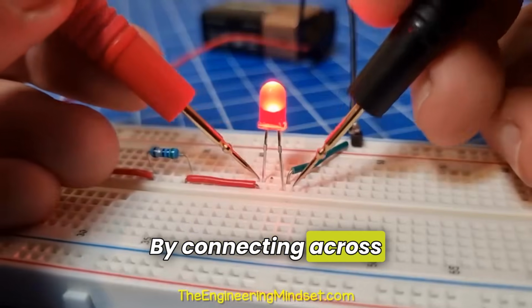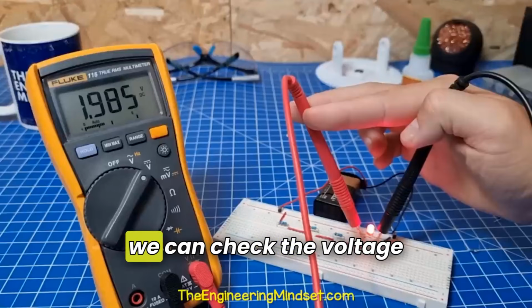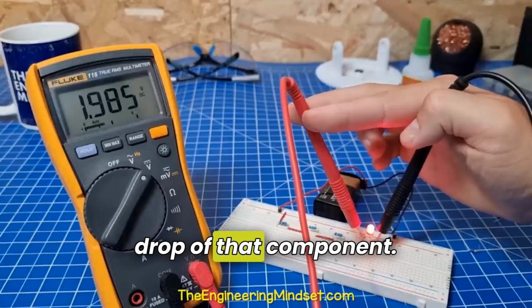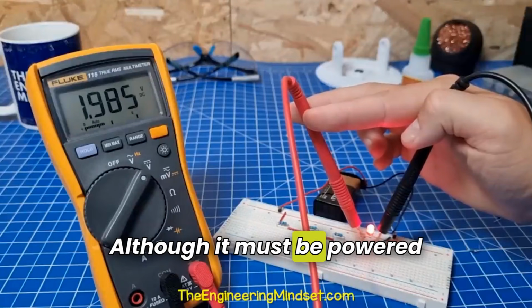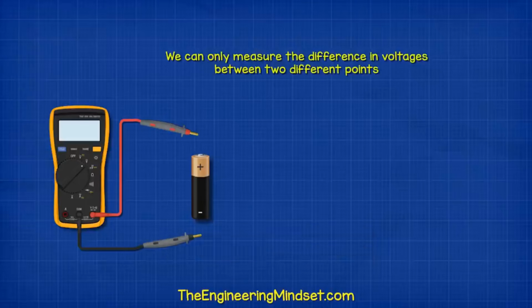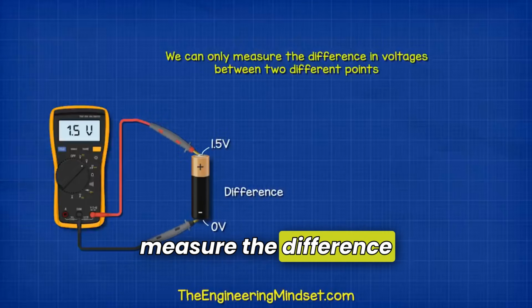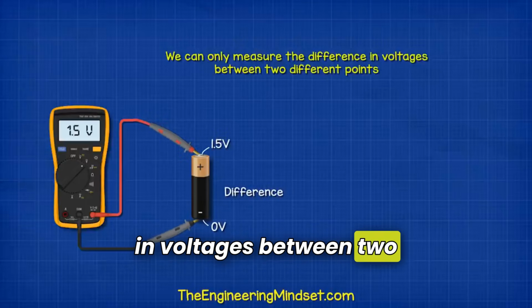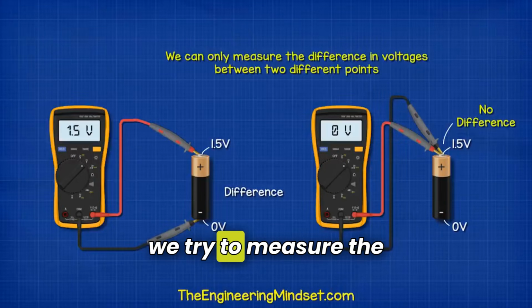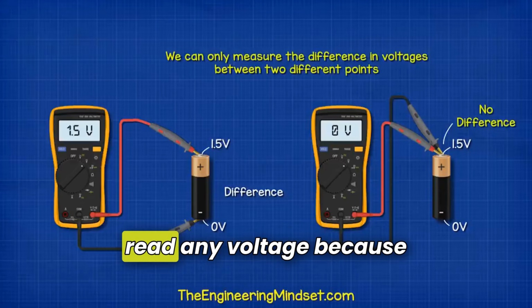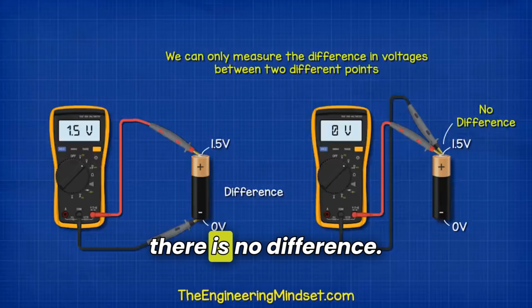By connecting across individual components, we can check the voltage drop of that component, although it must be powered in order to do this. Remember, we can only measure the difference in voltages between two different points. If we try to measure the same point, we won't read any voltage because there is no difference.